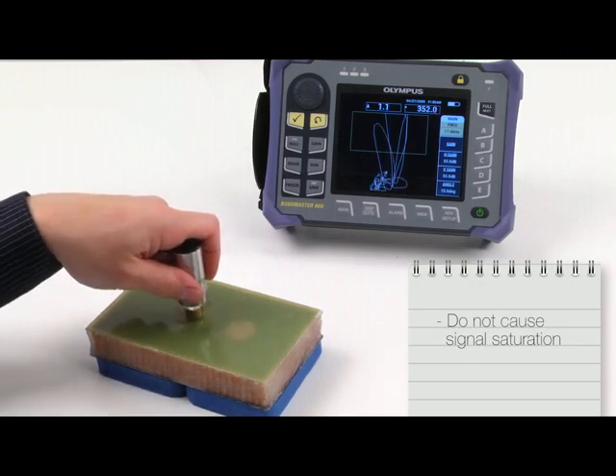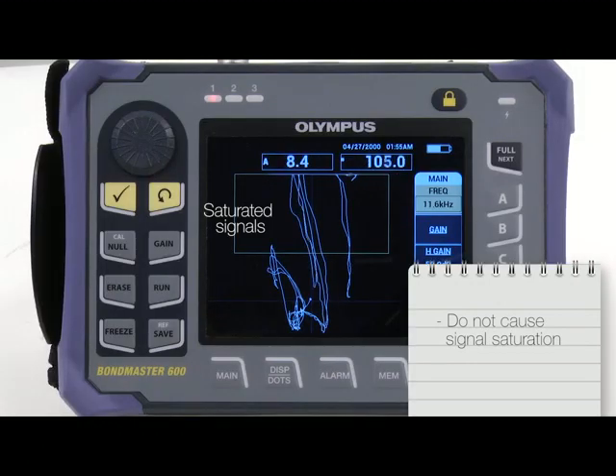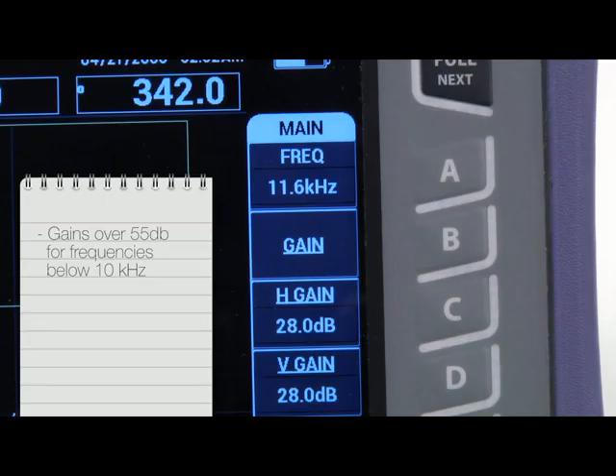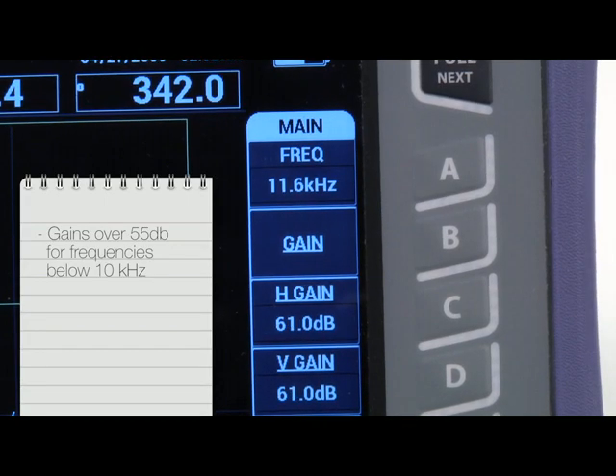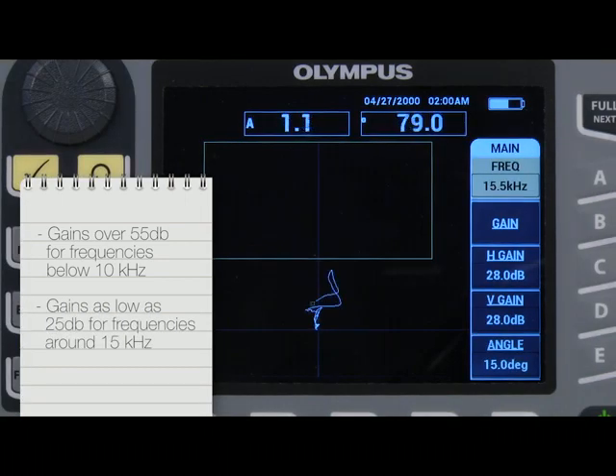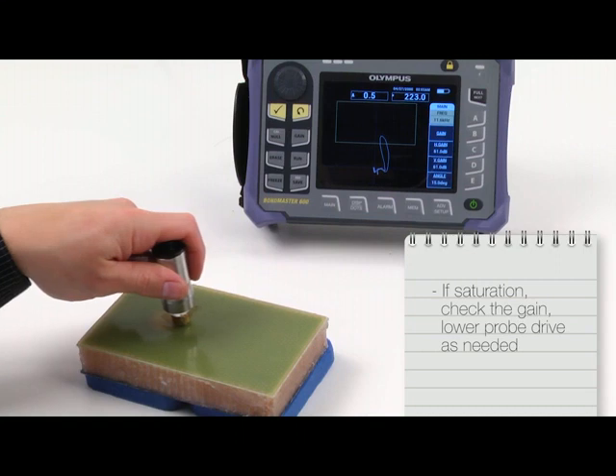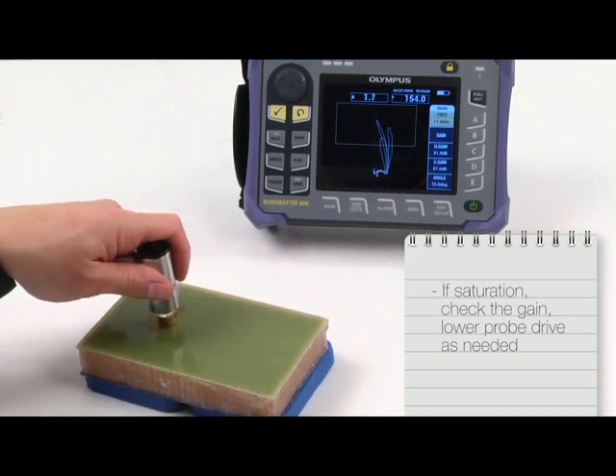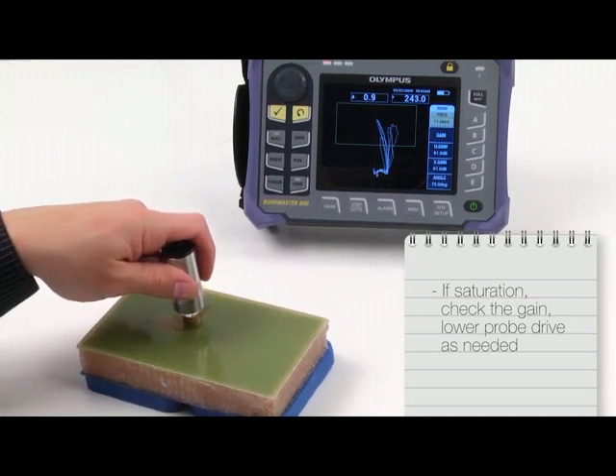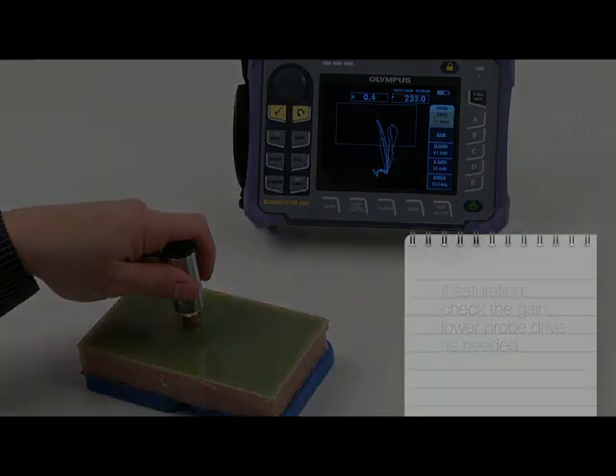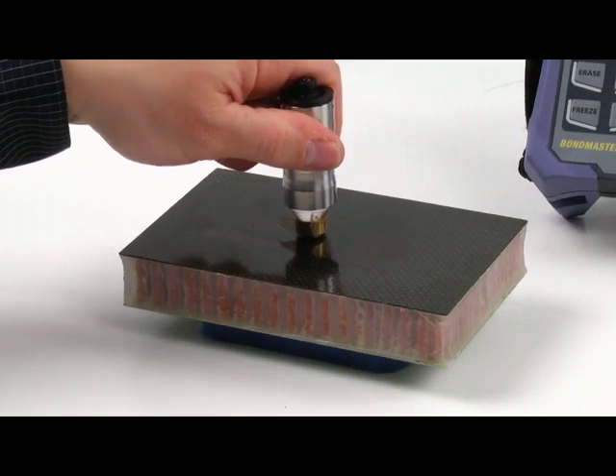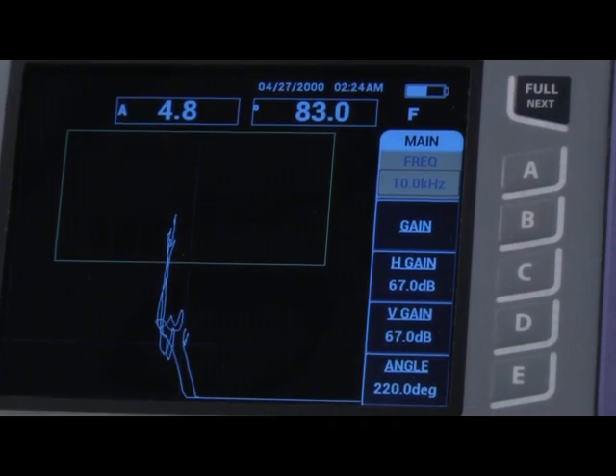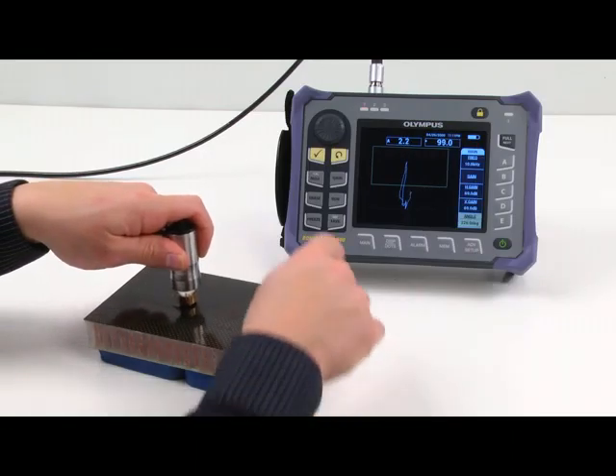the combination of gain and probe drive does not cause signal saturation. Be aware that gains over 55 dB may be needed at frequencies below 10 kHz, but gains as low as 25 dB may be required at frequencies around 15 kHz. In summary, if you observe or suspect saturation, remember to check the gain and possibly lower the probe drive as needed.